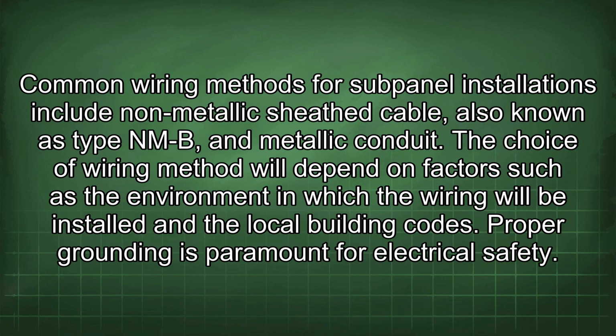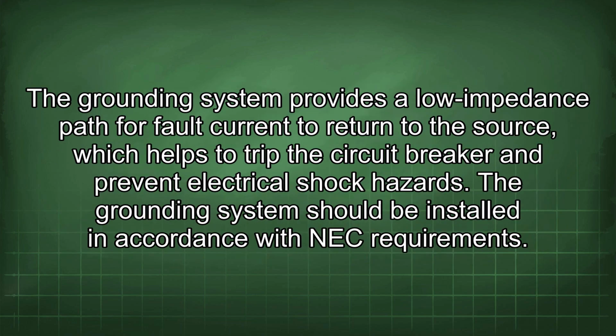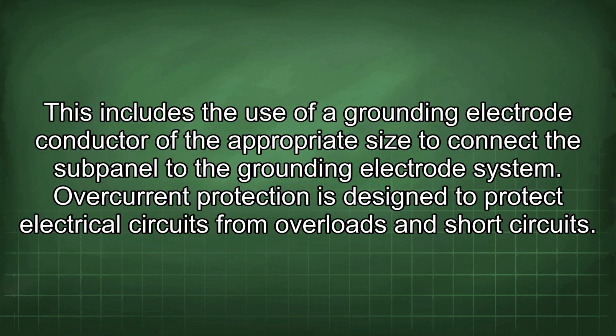Proper grounding is paramount for electrical safety. The grounding system provides a low impedance path for fault current to return to the source, which helps to trip the circuit breaker and prevent electrical shock hazards. The grounding system should be installed in accordance with NEC requirements. This includes the use of a grounding electrode conductor of the appropriate size to connect the subpanel to the grounding electrode system.